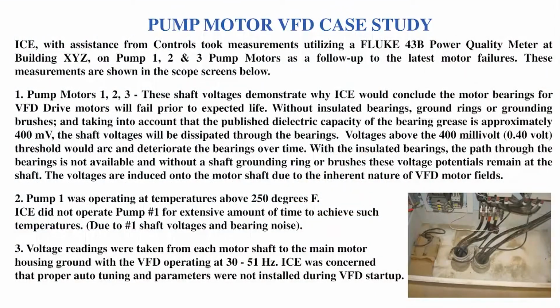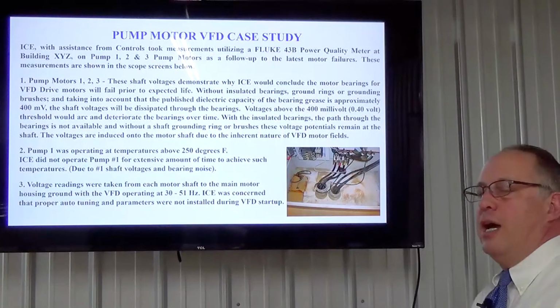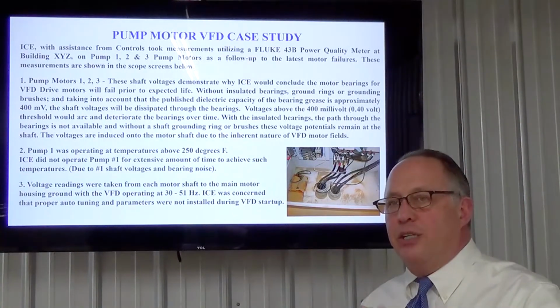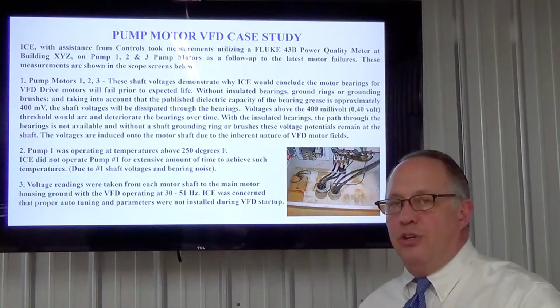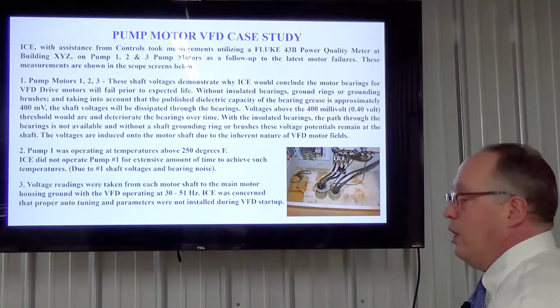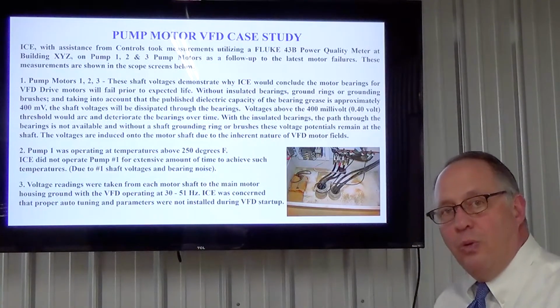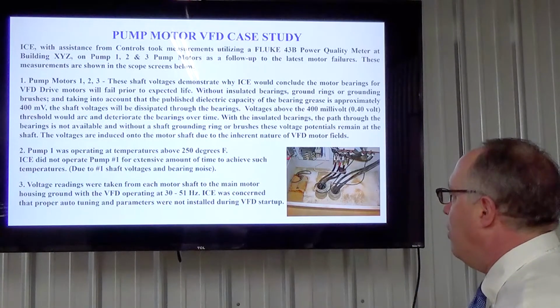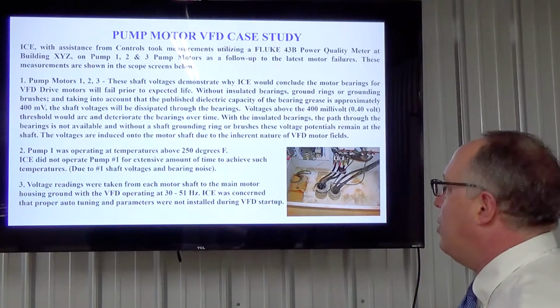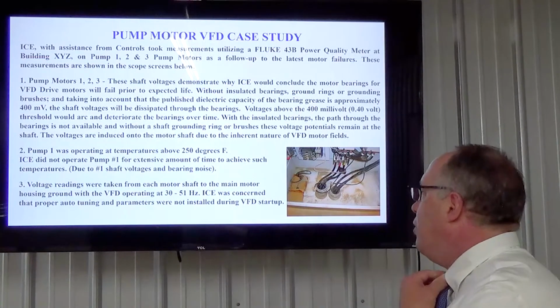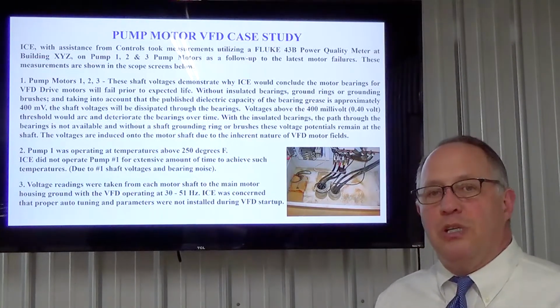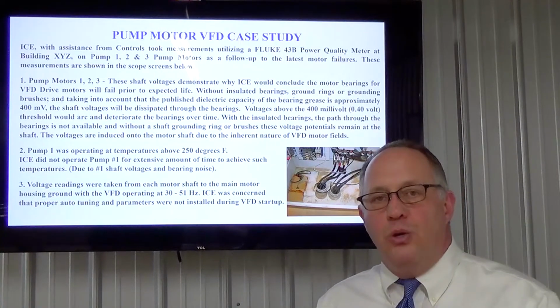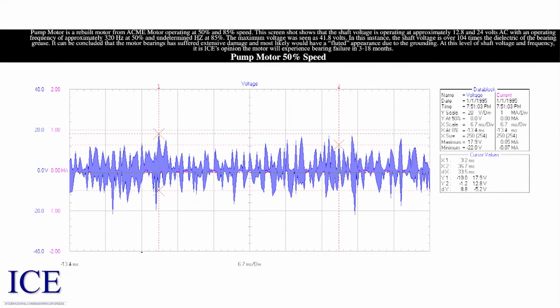Voltage readings were taken from each motor shaft to the main motor housing ground, with the VFD operating at between 30 and 51 hertz. We stopped at 51 hertz because that was the maximum based on the calculations for what it was going to be used for. So in other words, we were measuring exactly what the pump was going to be doing in the real world. I was concerned that proper auto-tuning and parameters were not installed during the VFD startup, so we had those particular parameters retuned, and we still came up with the measurements. These are the actual measurements that we saw.